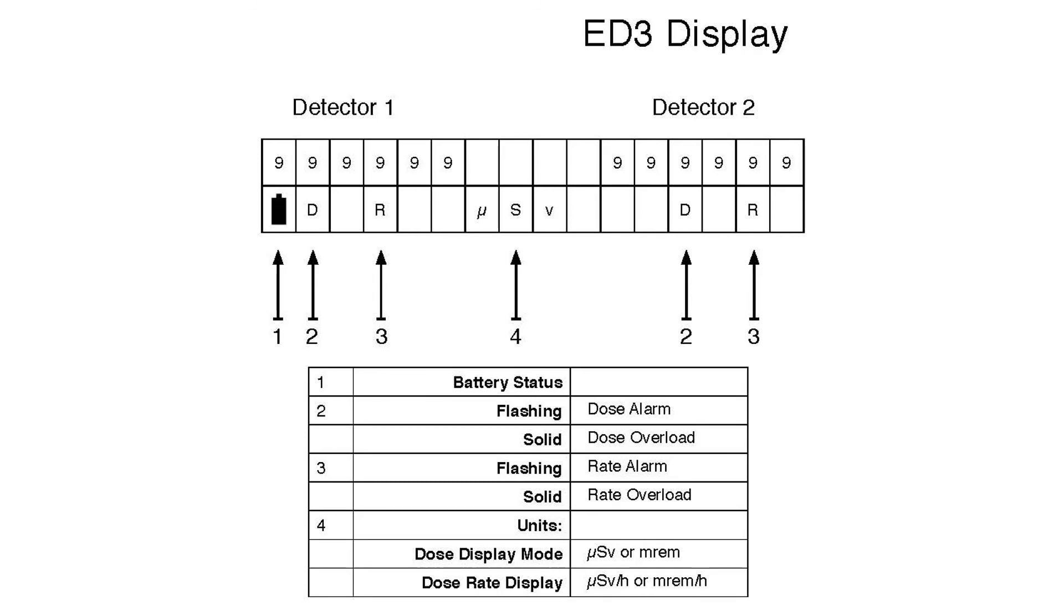The ED3 has two lines of display. The top line is numerical information for the dose or dose rate value. The bottom line is status, such as battery status, whether the unit is in dose or dose rate mode, for D or R, and also the units of measure, whether they be SI or US units. It's divided in half. On the left is detector one and on the right is detector two. Normally, the display is in a solid mode, either with the backlight on or off.